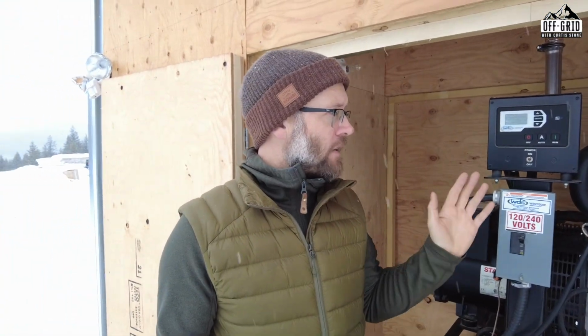And then the last one, which is the 30 seconds or a minute, is for when suddenly a big load spikes in and those other triggers didn't work because they don't work for that type. All of a sudden a big load comes in and whoa, your batteries are draining fast, boom, the generator will kick on. So far this whole winter, it's worked really well. I was managing it for a while because I was actually nervous. I didn't trust the triggers at first. And I just had to relax and let it go, and it's performed perfectly.